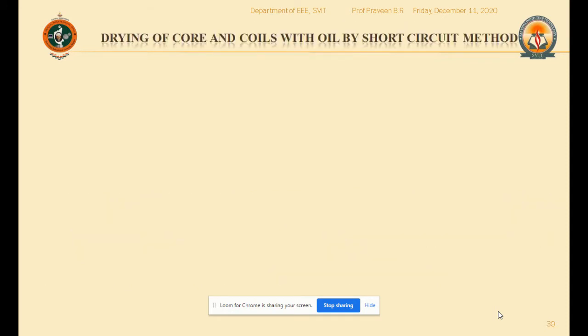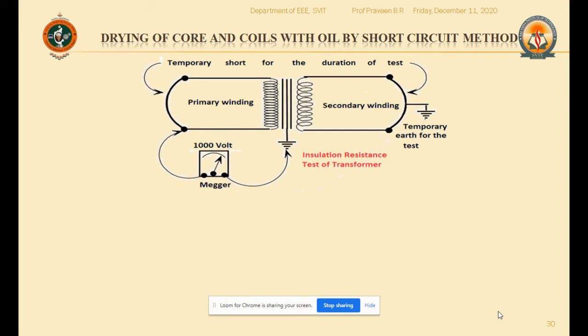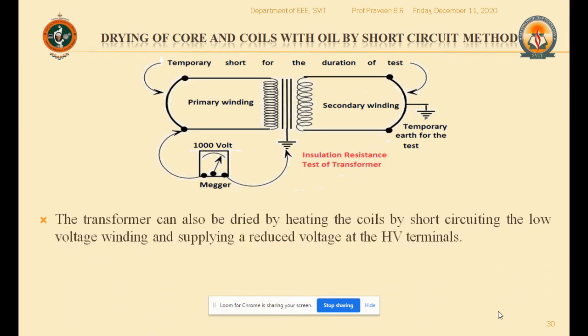The insulation resistance is then checked to make sure whether the coils are dry or not. The second method is called the short circuit method, in which you have primary windings and secondary windings, where it has been connected. The primary winding is connected to the megger through the ground. The insulation resistance test of the transformer is measured. The secondary windings are temporarily earthed for this particular test.